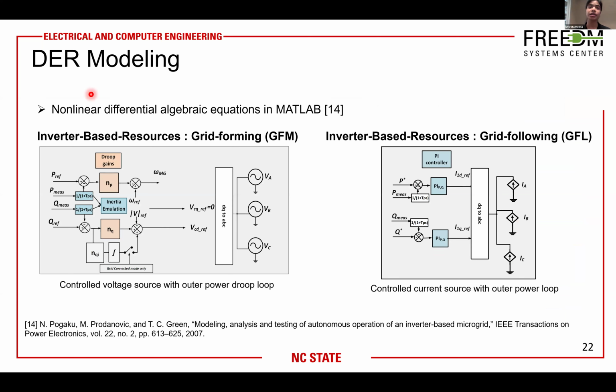This is how the DERs are modeled in the framework. For each DER, we develop a nonlinear differential algebraic equation-based model in MATLAB. The grid forming inverter is modeled as a controlled voltage source with the outer power droop loop, and the tunable parameters are the droop and the low pass filter gain. For the grid following inverter, it is modeled as a controlled current source with an outer power loop, which is a PI control loop, and the tunable parameters are the gains of this PI controller.